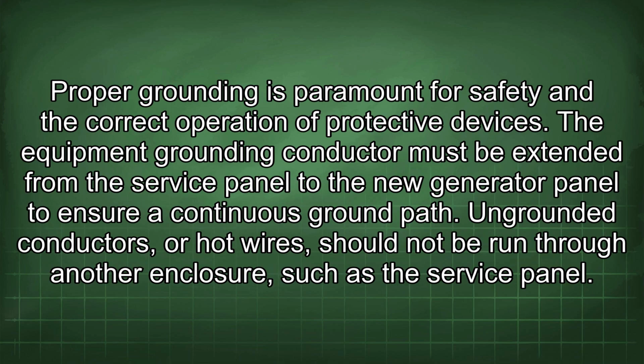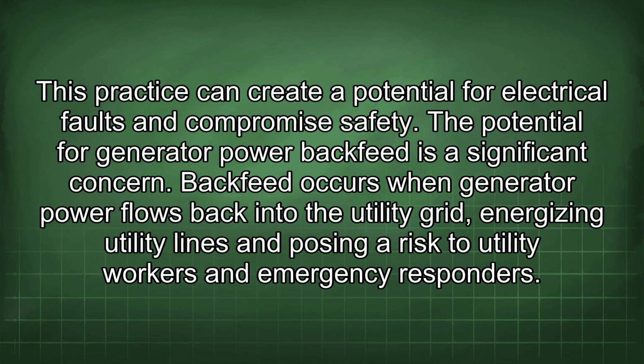Proper grounding is paramount for safety and the correct operation of protective devices. The equipment grounding conductor must be extended from the service panel to the new generator panel to ensure a continuous ground path. Ungrounded conductors, or hot wires, should not be run through another enclosure, such as the service panel. This practice can create a potential for electrical faults and compromise safety. The potential for generator power backfeed is a significant concern.